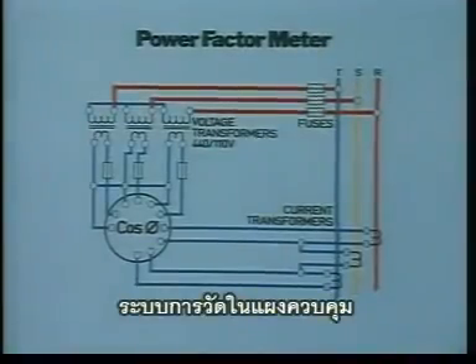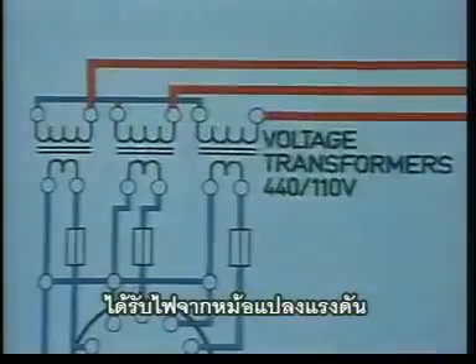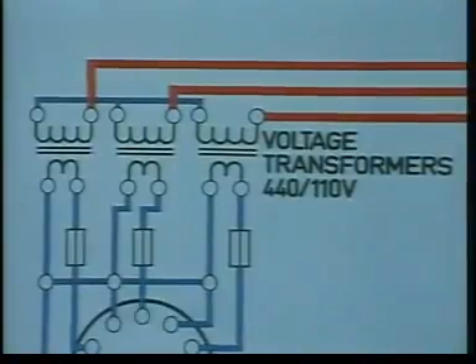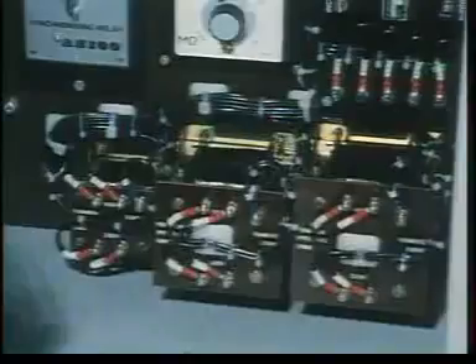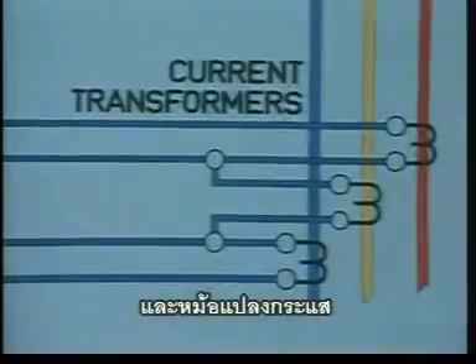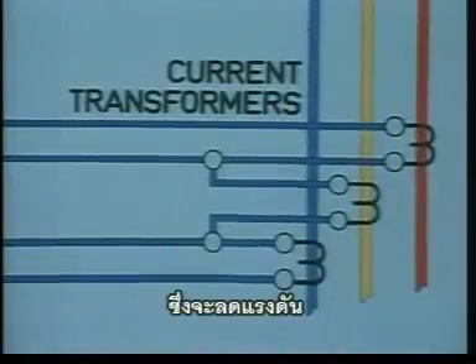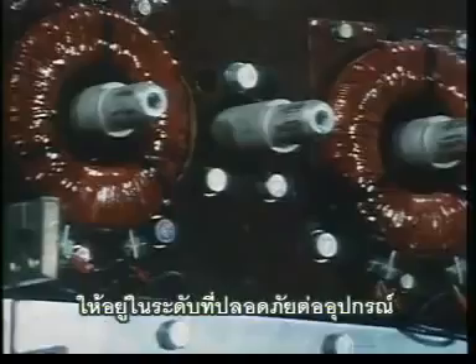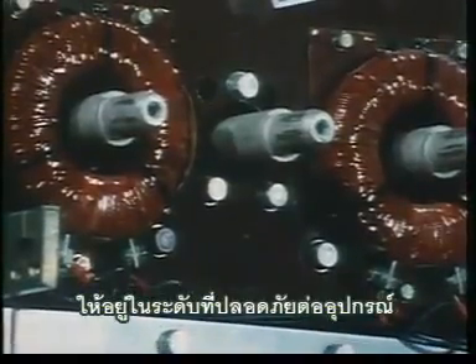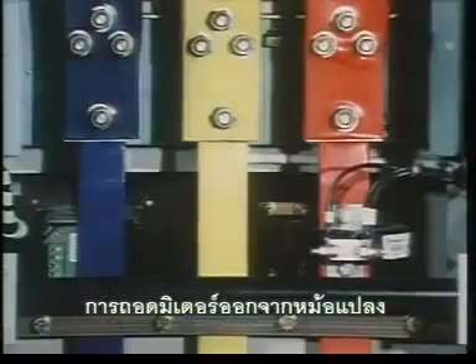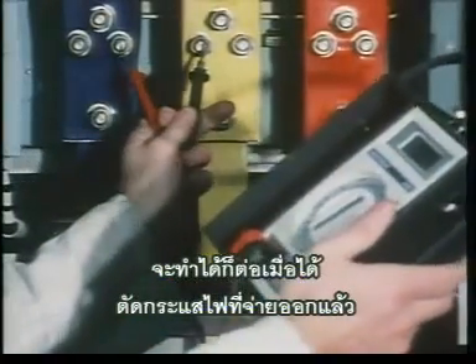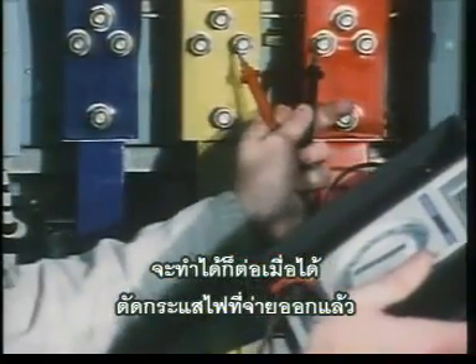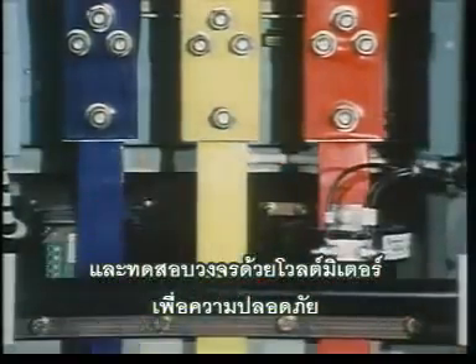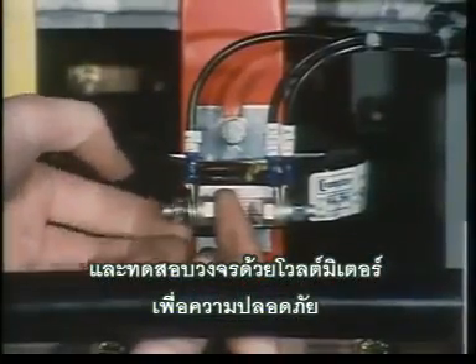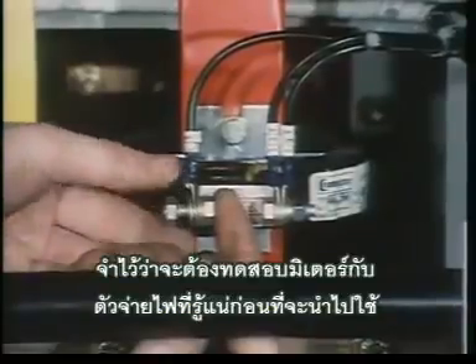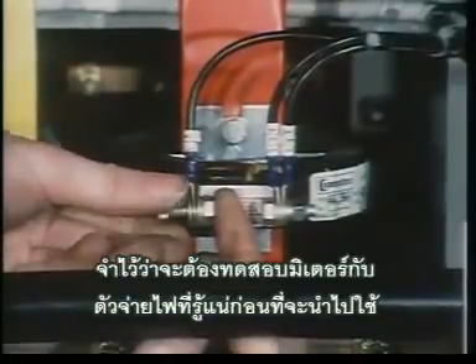The metering systems inside the switchboards are fed by voltage transformers and current transformers, which step down the circuit voltages and currents to safer levels for use in the instruments. Disconnecting a meter from a current transformer must only be done when the supply is off from the section monitored and the circuit is tested by a voltmeter to be safe. Remember to test the meter on a known supply before using it.